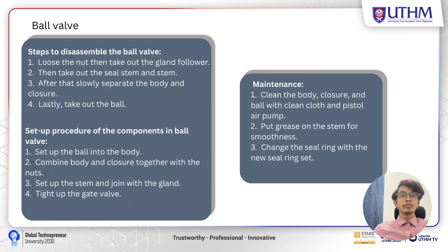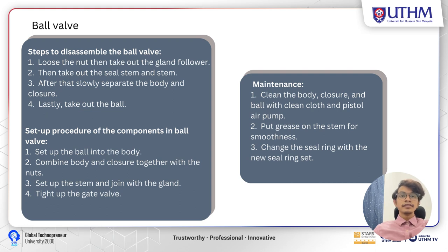For the ball valve, the steps to disassemble are: loosen the nut and take out the gland follower; take out the seal stem and stem; slowly separate the body and the closure; and lastly take out the ball. To reassemble: set up the ball into the body; combine the body and closure together with the nuts. For maintenance, clean the body, closure, and ball with clean cloth, and if necessary use a pistol air pump. Put grease on the stem for smoothness and change the seal ring with a new set.